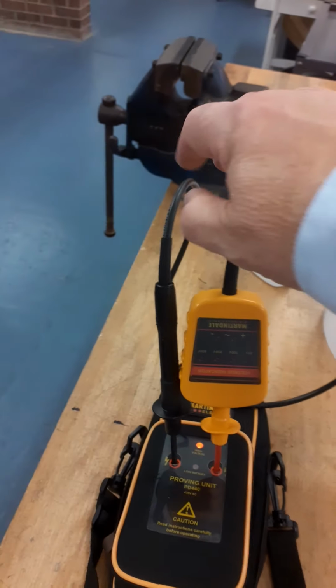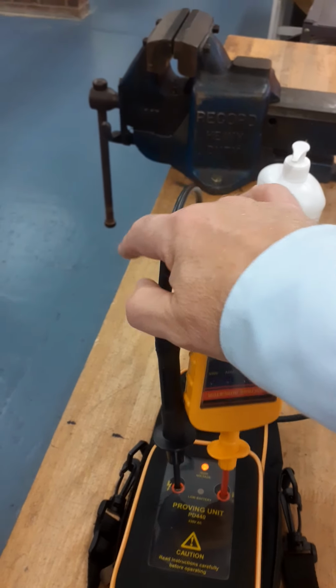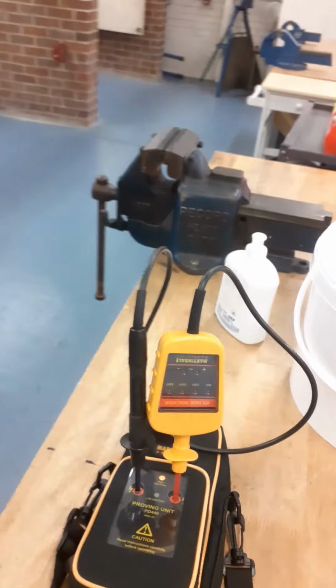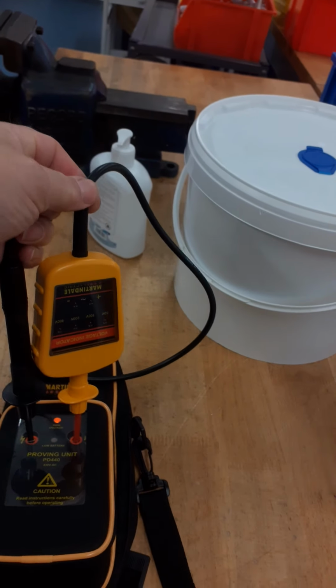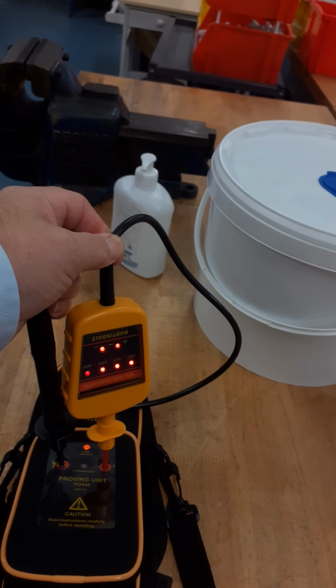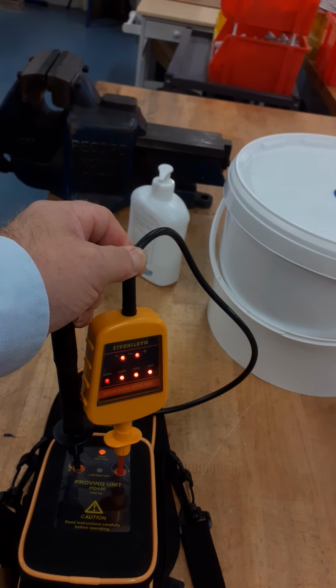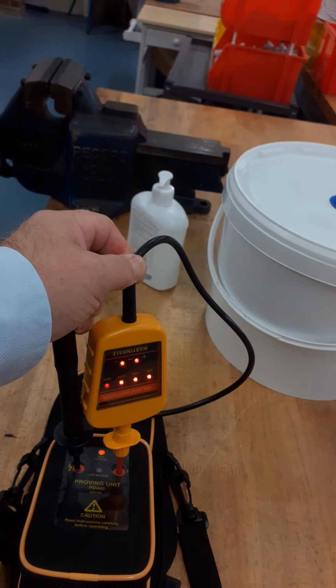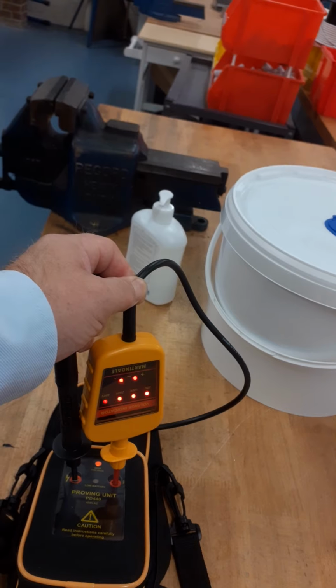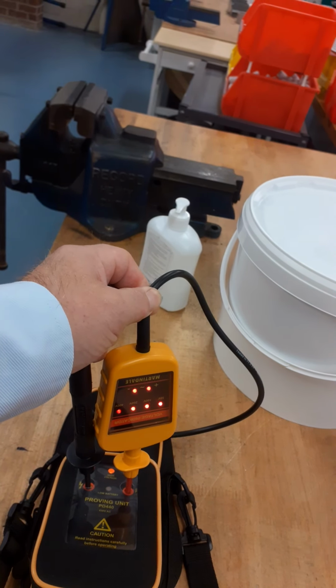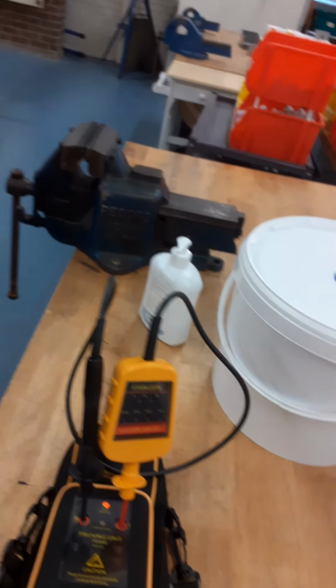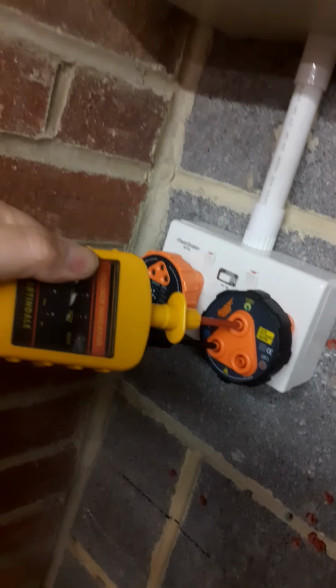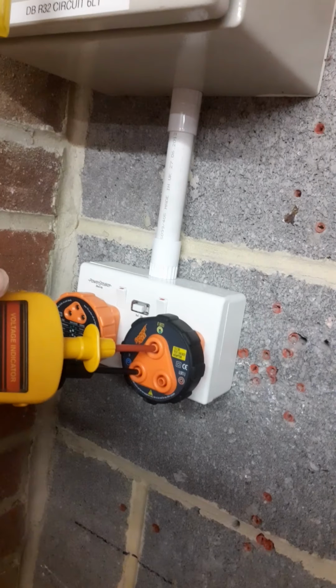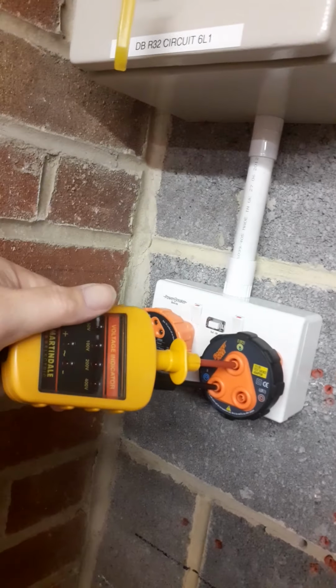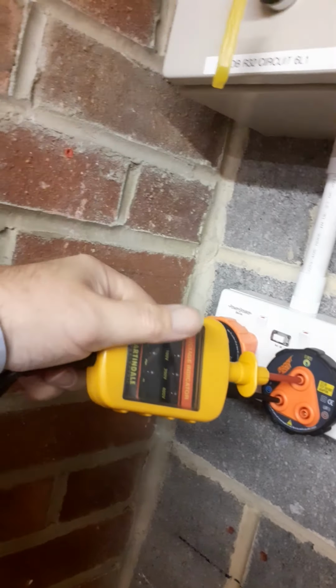So the voltage indicator is then inserted into the proving unit to make sure it is actually operational and working. Make sure that lights up. This has to be done twice, before and after, ensuring the supply is dead. Next, we go to the supply and we do 3 tests. Test 1 is you insert the probes between earth and neutral.